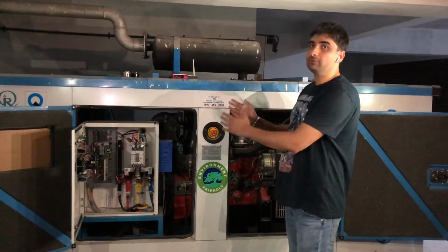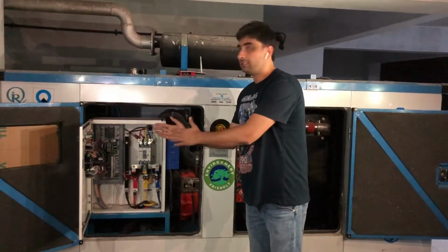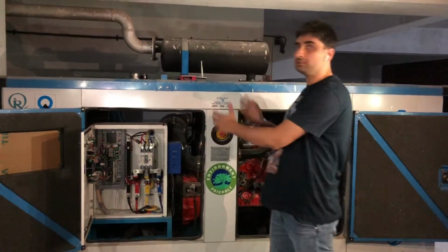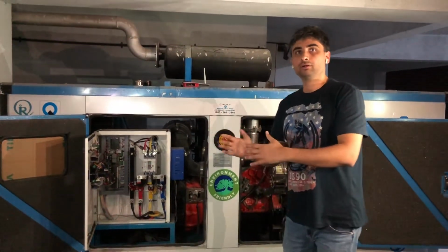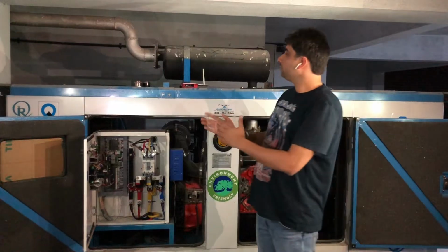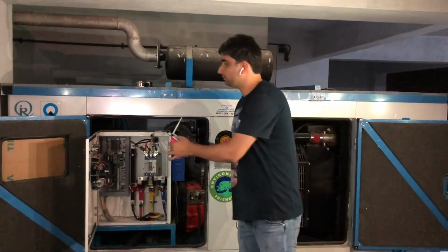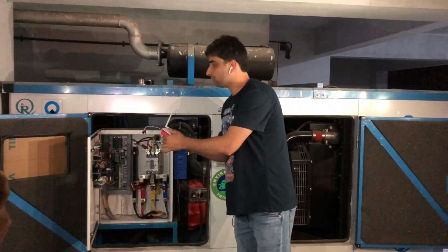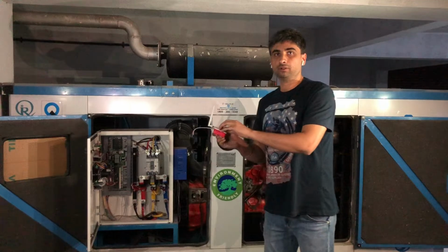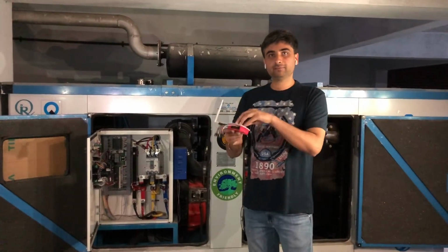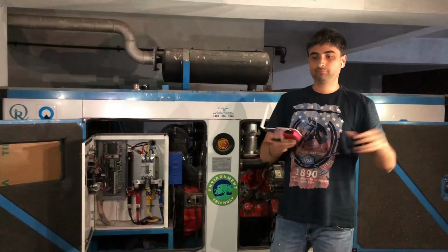So this is a 62 kVA diesel genset which has an inbuilt microcontroller which helps us to get the vital information about this generator such as the fuel level, the temperature or the RPM. So what we have done is we have built this device which we can directly connect into this microcontroller and get all the vital information into this device over Modbus protocol. So once the data is received into this device, we send it to Azure IoT Hub using MQTT protocol.